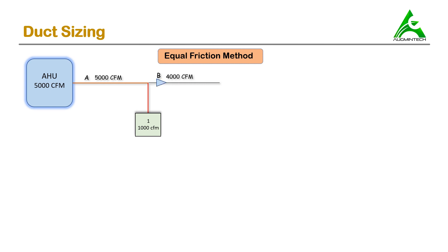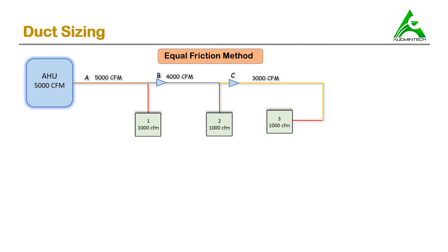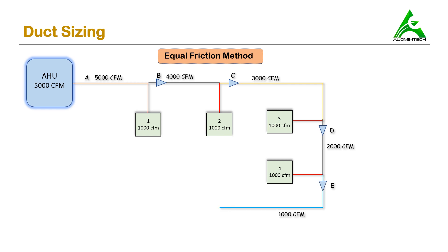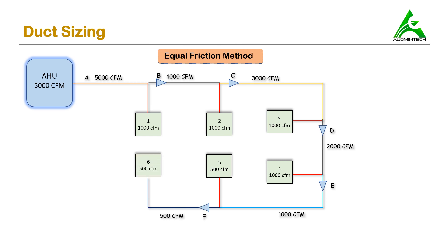The remaining 4000 CFM passes through the reducer to section B of the main duct. From this 4000 CFM, 1000 CFM is taken by diffuser number two, and the remaining air flows through section C. Out of this, 1000 CFM is taken by diffuser three, 1000 CFM by diffuser four, leaving 1000 CFM flowing through section E. From this, 500 CFM goes to diffuser five and the remaining 500 CFM to diffuser six. So there are six diffusers total.